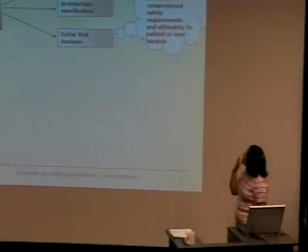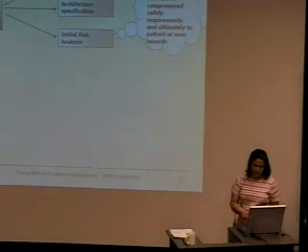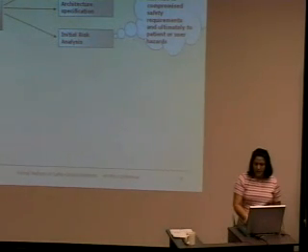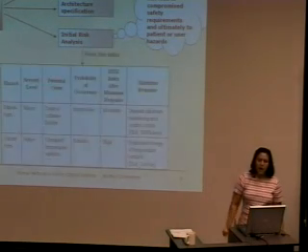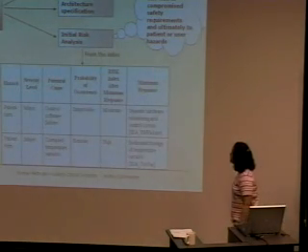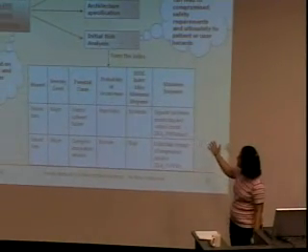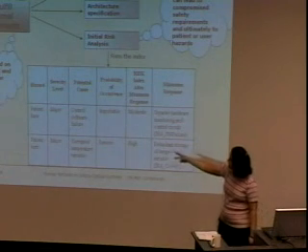Initial risk analysis specifically involves how a software failure leads to a patient hazard and what the consequences of it are. For example, the first thing to do for the initial risk analysis is to provide an index table. This is an example of the initial risk analysis.